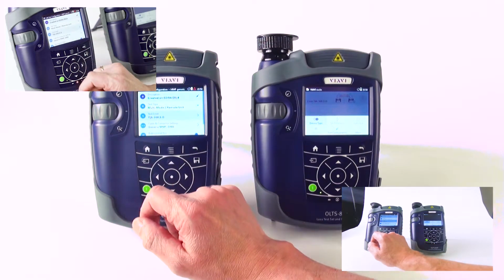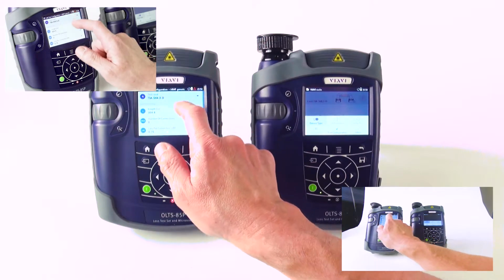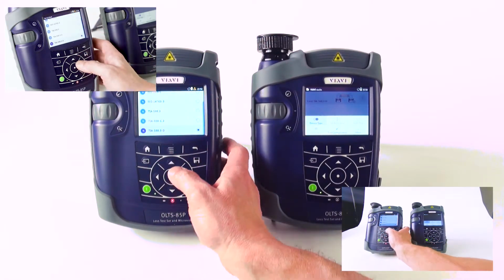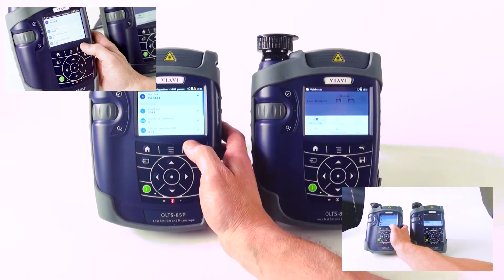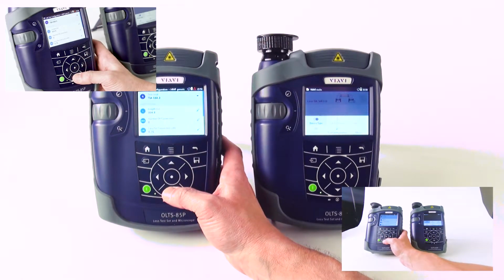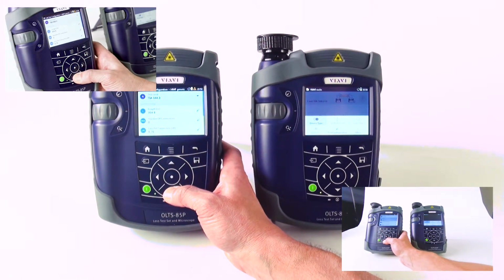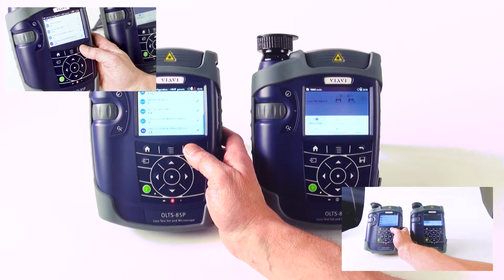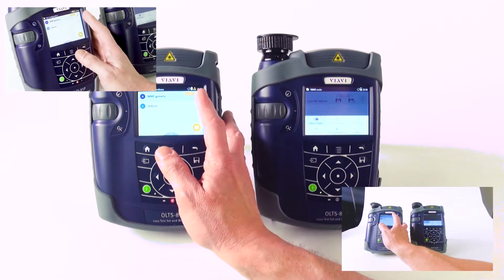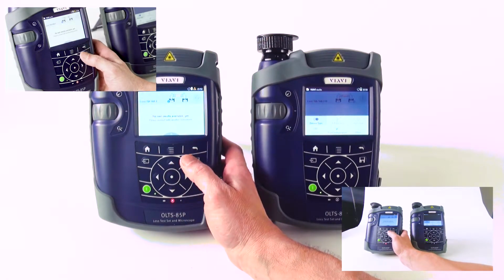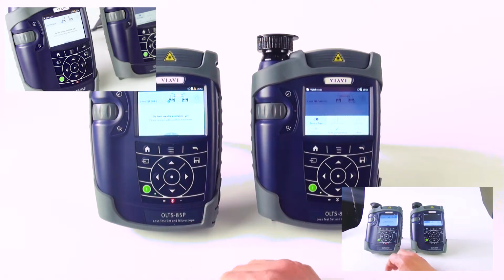The one I'll go into a bit here is your test limit. When you go into your test limit, you have many different choices as to what you can set. If you're in one of the TIA or IEC limits that is calculated, it asks for the limit for your length, the number of connections you have, loss per connection, number of splices, loss per splice, and your dB per kilometer loss at 850 and 1300 nanometers. With all that set up, I make sure it's set active, and at this point I'm ready to perform my set reference, which is our next video, and then I proceed on to testing.